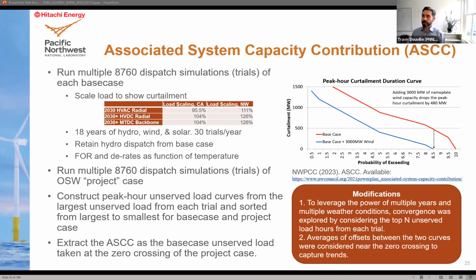A lot of people don't know that when you get above, if you're at 100 degrees inland, your wind park, those wind turbines are not probably operating at their nameplate capacity, even at nameplate wind speed. And that has to do with how hot they get and the cooling systems that are installed on those turbines. On an individual turbine basis, that's not a big deal. But when you think about an entire park or collections of parks, and you start rolling out 400 megawatts, gigawatts, it becomes important. So we wanted to make sure we had captured those effects.